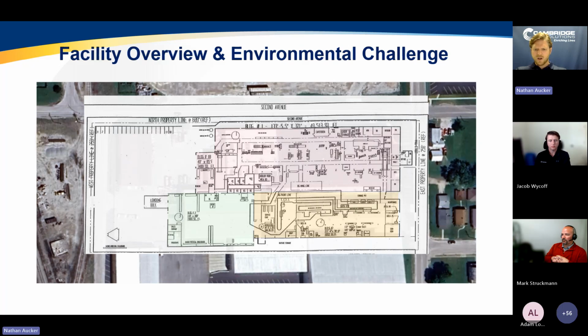And a lot of these facilities solve their problems just through ventilation. So they have a large exhaust load, and they either have open doors where air is coming through, and you're really trying to drive that temperature down to as close as possible to the outdoor air temperature, which is much better than no ventilation. It's much better than not doing any of these things, but it still can be difficult if the temperatures are up in 95 or 100 degrees Fahrenheit. And so after researching options with the customer, we decided to use a 2-stage, and we'll jump through here.